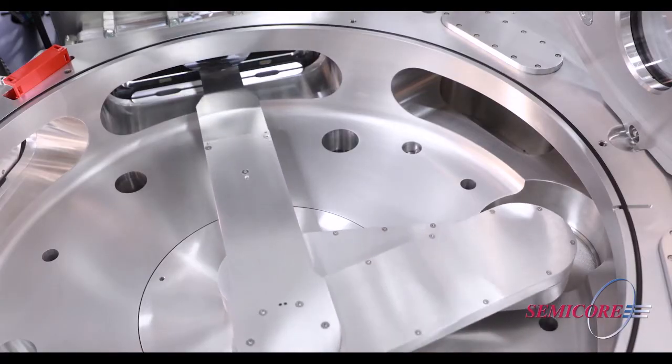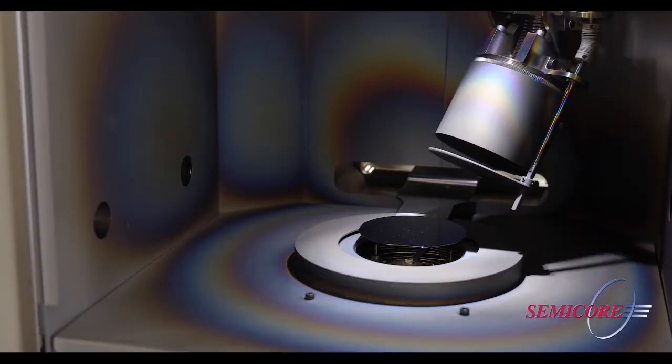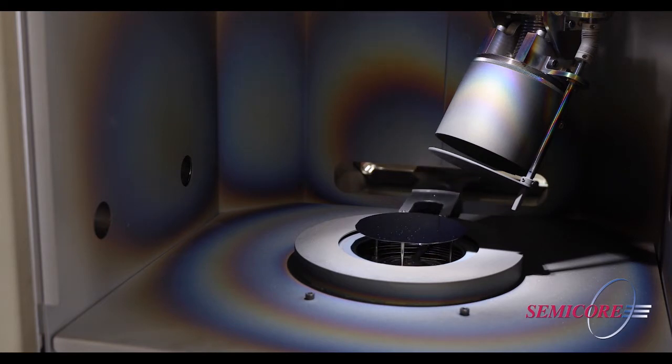The robot places a wafer into a deposition module where it is lifted from the robot end effector and placed on the substrate table. The robot then retracts from the module to allow processing to begin.